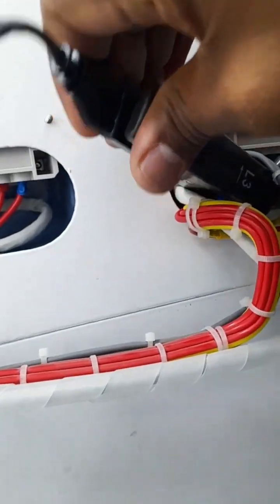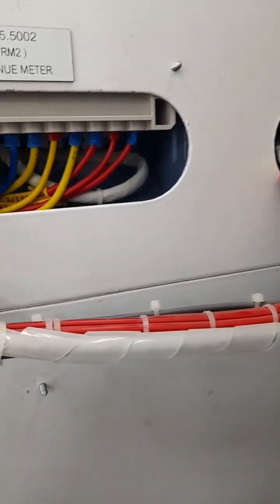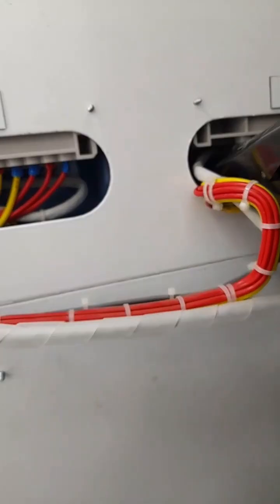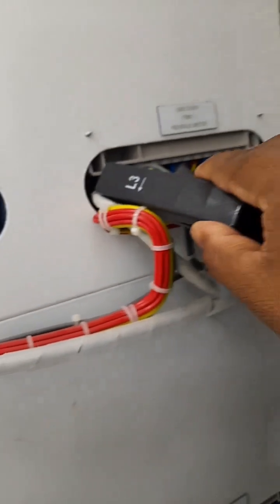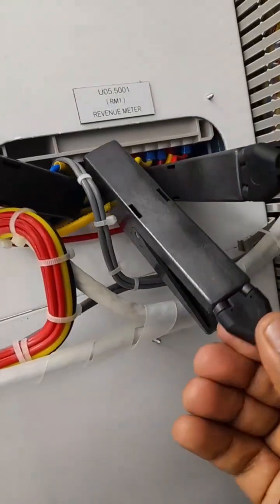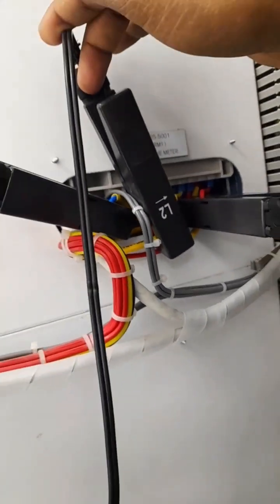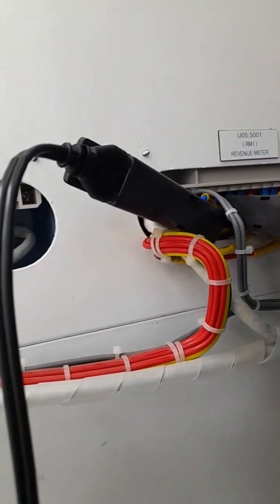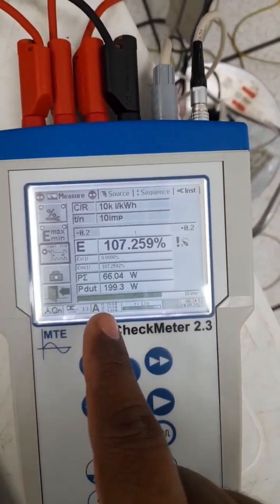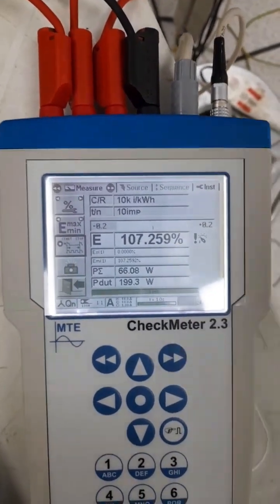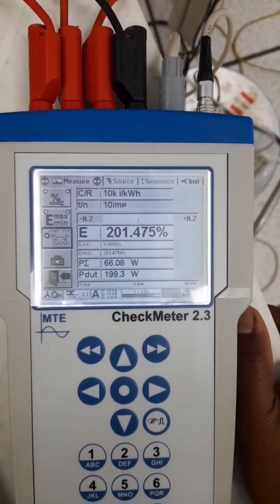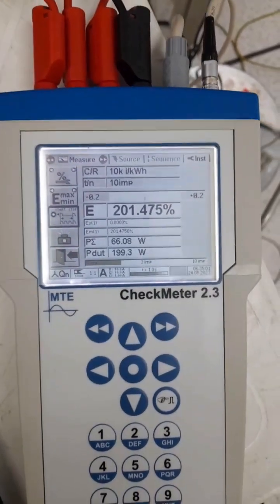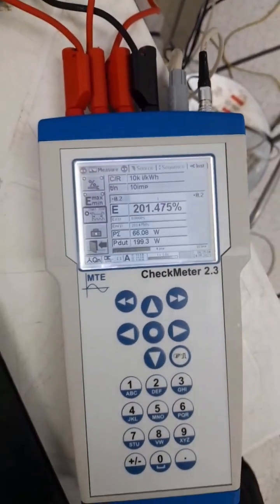Now I changed this clamp direction. The clamp direction was changed. Now the current direction is outward. At the same time, it should be fixed properly. If it is like this or like this, it's not accepted. Your error will be high. Maybe you will not get the exact accuracy reading. See now the power is completely down. Before it was around 199 point something, but actual now is 66. This is because the current direction is reversed, so the clamp is very important.